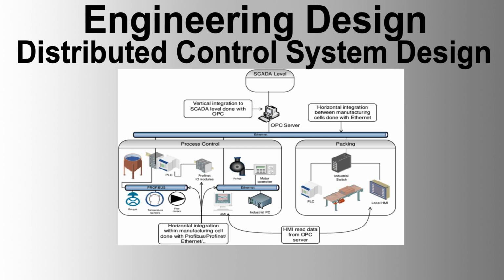5. Power Management System, PMS. The PMS must be incorporated into the DCS to provide fully integrated power generation and distribution. The system must graphically display the electrical network, monitor and trend power generation inputs, display and record non-process alarms, and perform event recording with 10 milliseconds accuracy. It must allow manual synchronization of generator electrical supplies and implement load shedding if available power generation cannot support the load. The DCS must monitor generator output and initiate load shedding based on a pre-configured priority list to prevent system collapse during generator failure.